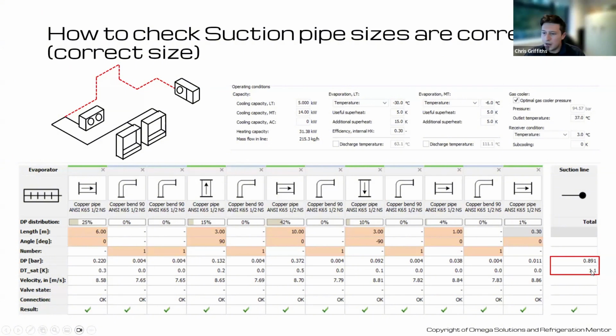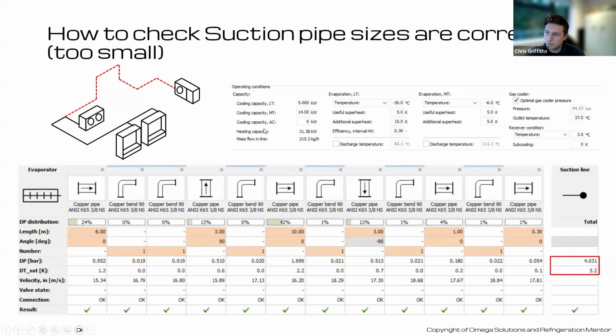So here we go. We've got our value there. But again, that's what happens now if we go for 3/8 pipe instead. And lo and behold, that 1.1 has become 5.2. So from that, we can effectively guarantee that is an issue with that pipe size. Ah, so yep, someone's already jumping ahead of us in the chat here with what to do next.